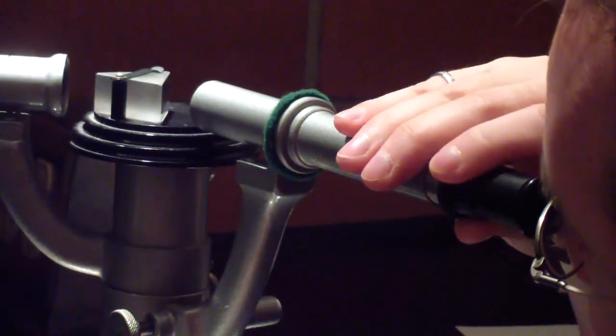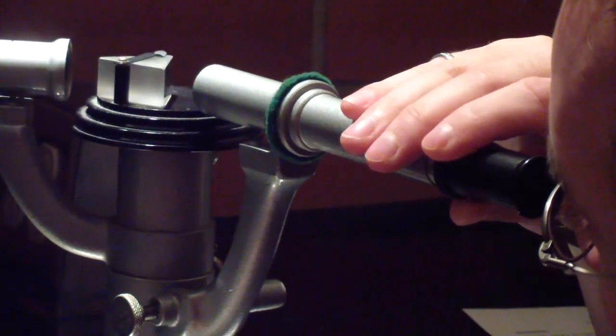Note that you may also push in or pull out the slit adjust assembly at the other end of the collimator. At the front of the collimator, there is a knob to adjust slit width.